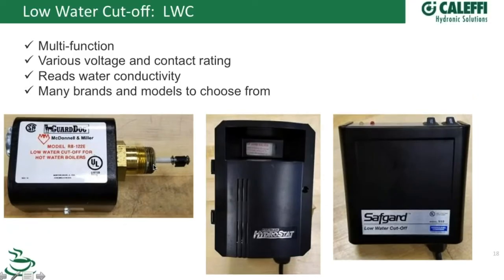One important thing on low water cutoff switches is where you put this. It's usually going to be installed at the highest point in the piping system. If you come out of the top of a ModCon boiler, for example, you want to put this up above the highest point in that piping so that as soon as the water starts to leave that point, you detect it. Obviously don't put it below the boiler or on the side, because you could leak enough water out of the system and still have a dry fire condition. Follow the installation instructions that come with these devices.